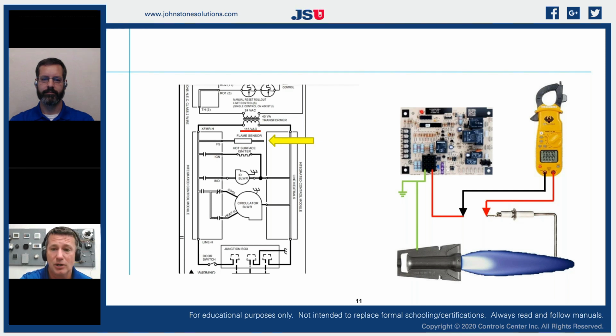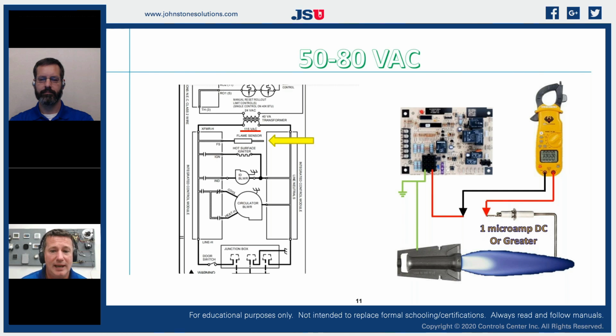We apply current to that wire. If we break that wire, just unplug it from the flame rod, and put our meter in series with that on the microamp DC setting, we will see above 1 microamp DC or greater on most control boards. Typically that's going to be significantly higher, even up to 10 or so. 1 is typically the trip point on most of the Honeywells that I encounter.